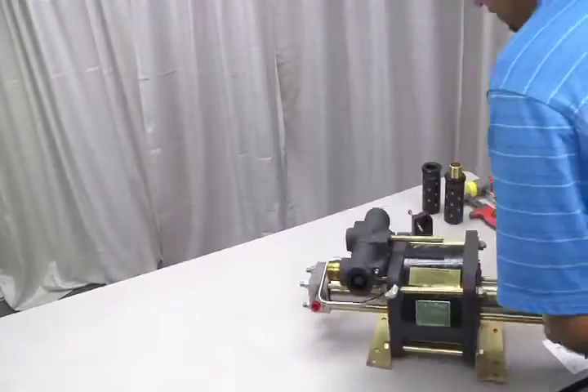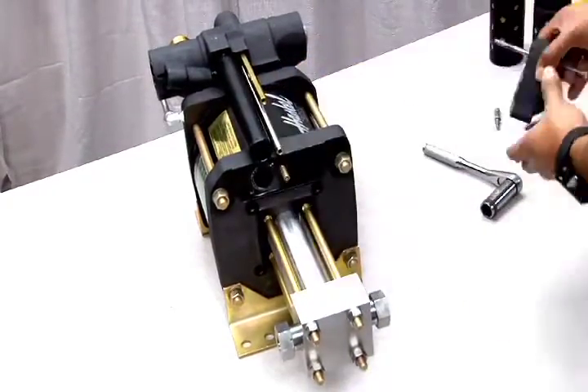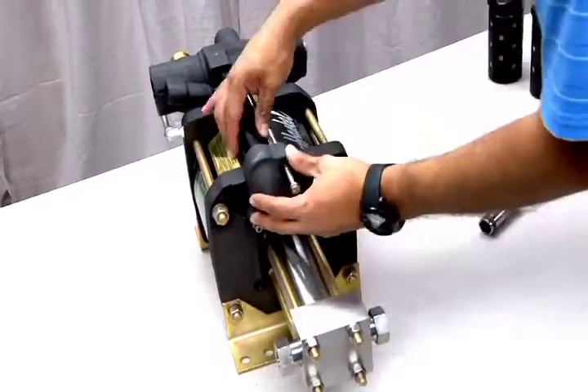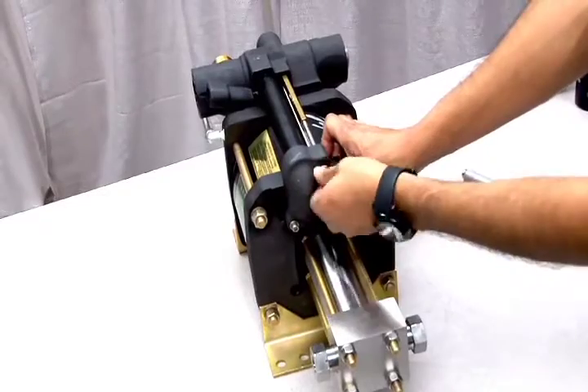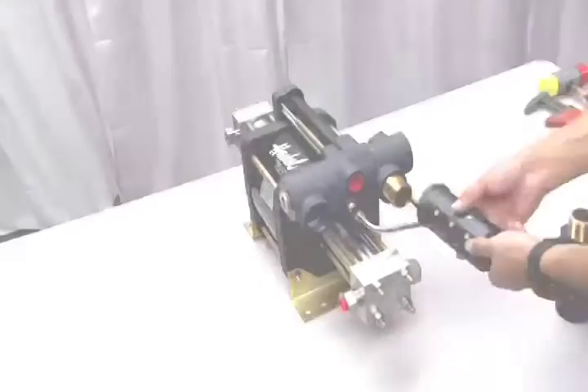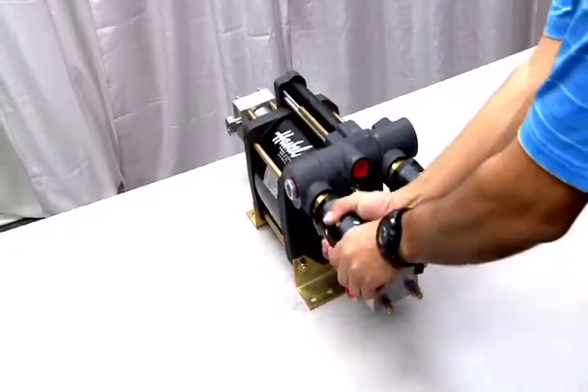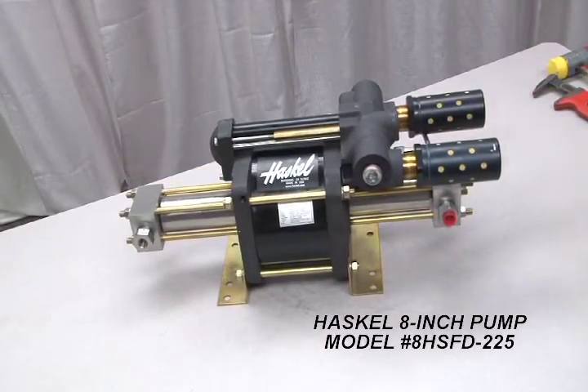Turn the unit back into an upright position and reinsert the pilot stems, flow tube, pilot tube, and the tube end cap. Make sure all tubes are properly aligned before tightening. There is no particular torque specification for these bolts — just make sure they're good and tight. Finally, replace the mufflers by screwing them back on. This completes the reassembly process for this Haskel 8-inch air drive hydraulic pump, model number 8HSFD-225.